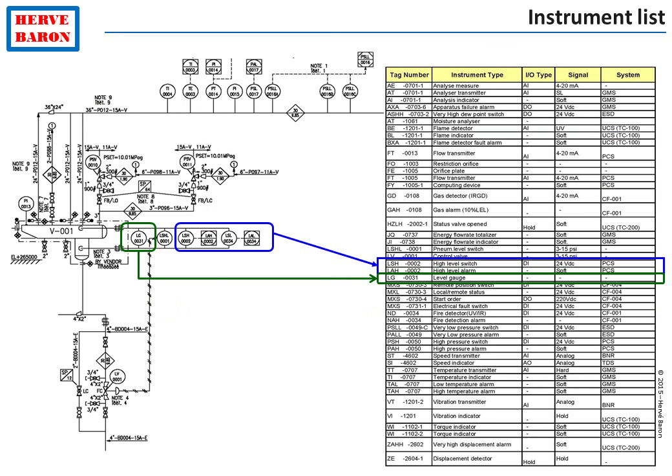The instrument engineer's first task is to produce the list of all instruments specified by process on the P&IDs. This forms the instruments list or instruments database, which is a central document for the instrumentation and automation discipline. It lists all the field instruments that need to be specified, as well as all the IOs — inputs and outputs — for the systems, and gives the capacity of these systems.